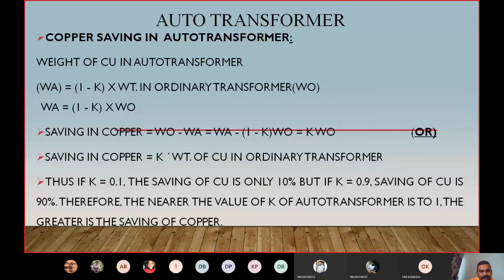So what we will do: saving in copper is equal to copper used in ordinary transformer minus copper used in auto transformer. Subtracting both will give us the saving in copper. So we can write: saving in copper is equal to WO minus WA. Now what is the equation for WA? WA is equal to 1 minus k multiplied by WO. Putting this equation in, it becomes WO minus (1 minus k) WO, which equals k into WO. So saving in copper is equal to k multiplied by weight of copper in ordinary transformer.